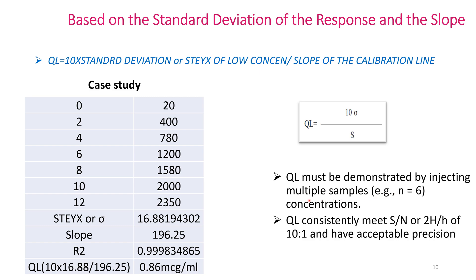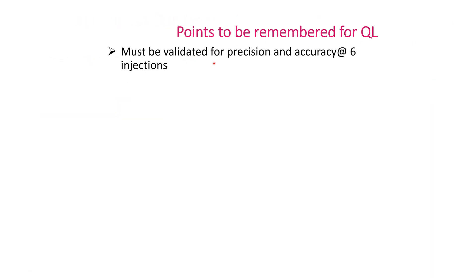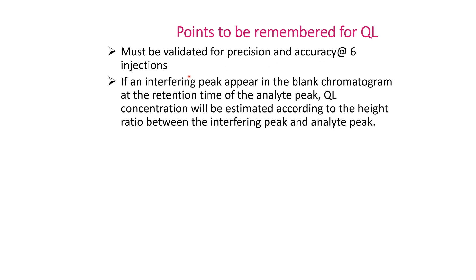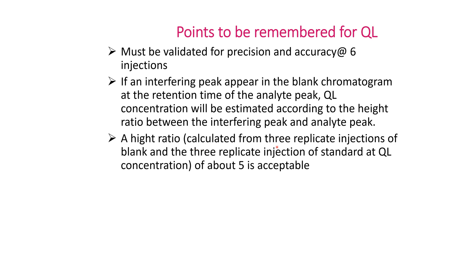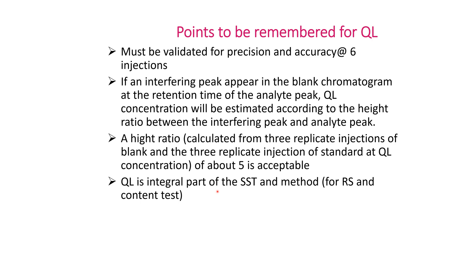QL must be demonstrated by injecting multiple samples — at least 6 injections. QL must consistently meet S/N ≥ 10:1 and have acceptable precision and accuracy. Key points: QL must be validated for precision and accuracy using 6 injections. If an interfering peak appears in the blank chromatogram at the retention time of the analyte peak, QL concentration will be estimated according to the height ratio between the interfering peak and analyte peak. A height ratio calculated from three replicate injections of blank and three replicate injections at QL concentration of about 5:1 is acceptable. QL is an integral part of system suitability and method for related substances and content tests.